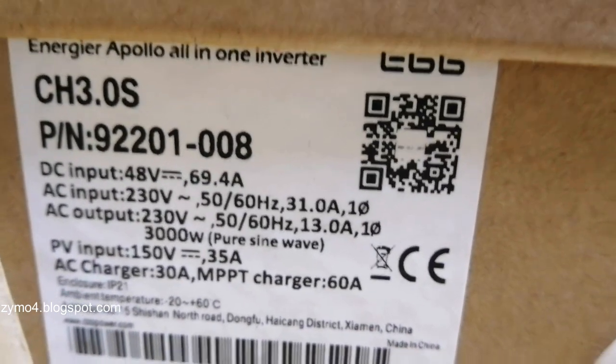Let's get a closer look inside — very robust hardware. On this side you can see the AC output 1: the line, the ground, and the neutral. Same thing on AC in. If you are line-to-line you can use L, L, and N. Remember when you power this up, your line, your grid, or your output will be L to N. It has torque specs — good thing it's really well designed — and it has its own description on how to tighten the screws.